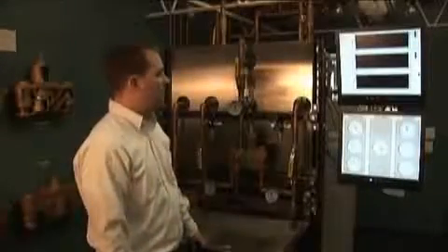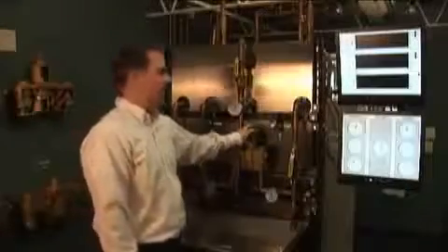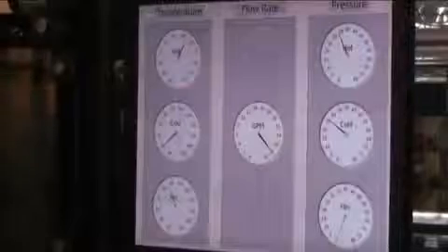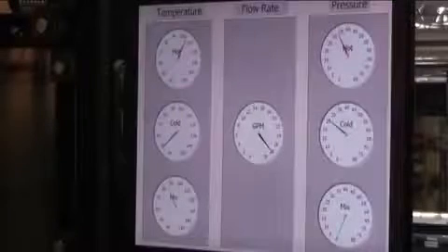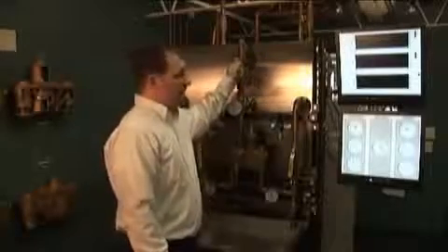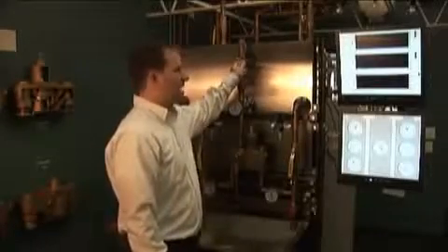Start the flow of water and let the instrumentation collect the data. You notice my mix temperature is lower in this case. Because I'm using an emergency mixing valve, we want a temperature that's lower than 90, 95 degrees. So this is set at about 85. This would be a typical flow rate if a drench shower or something like that was being used.